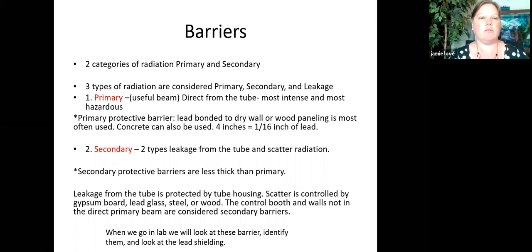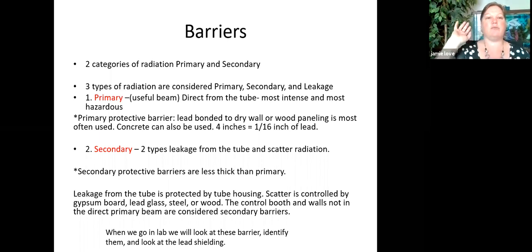So again, reviewing the barriers, they're going to protect us. If somebody's x-ray room is here and next door they're doing patient care, the primary barrier is going to protect that person in the next room from getting hit with x-rays through the wall. So a primary barrier is going to be in front of the tube, where the beam is directly pointing at it.